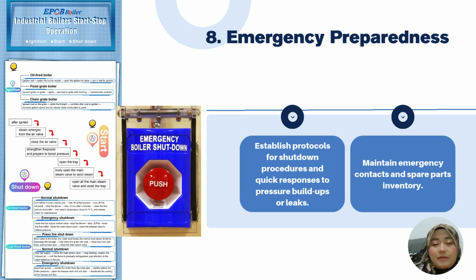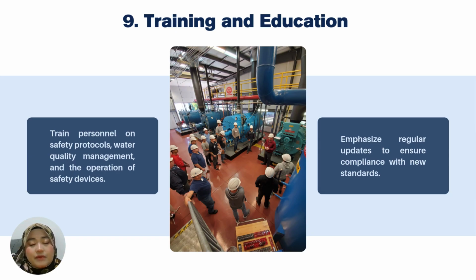Next, we have emergency preparedness. For emergency preparedness, it needs to establish protocols for shutdown procedures and quick responses to pressure buildup or leaks, and also maintain emergency contacts and a spare parts inventory. Another important procedure would be training and education. Train personnel on safety protocols, water quality management, and the operation of safety devices. It also needs to emphasize regular updates to ensure compliance with new standards.